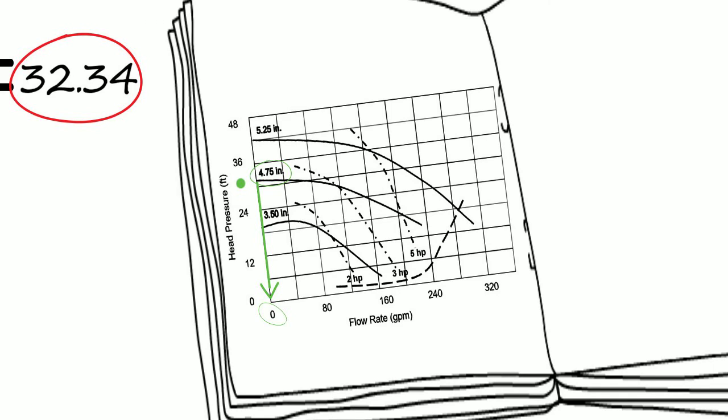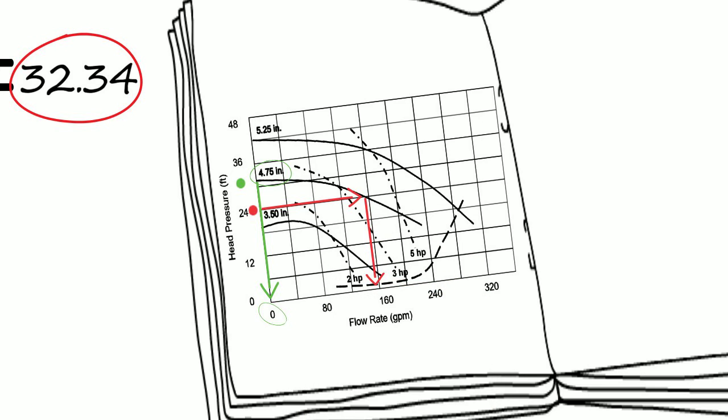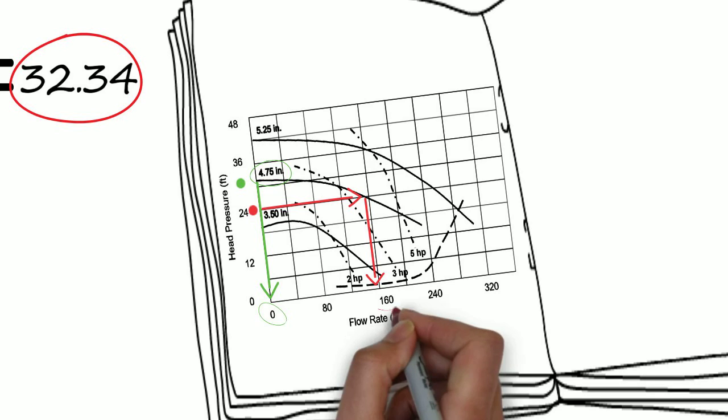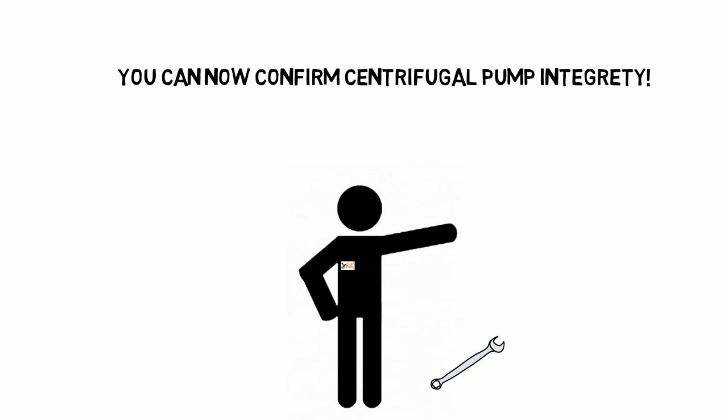What if it was reading something else? See, this is a good situation, the green. But what if we had a different reading? Say we had 24 feet of head. We draw an arrow over until it hits the 4.75 pump curve, draw an arrow down, and we're almost doing 160 GPM. Well, how can that be if the valve is shut? This is an indication that your pump reading is off. Either the impeller is worn, the cut water is broken, wear ring is off, motor speed is down. You can now confirm centrifugal pump integrity.